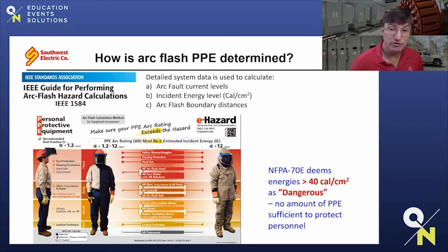This picture here gives you a visual on what kind of energies we're talking about. So the far left shows the very lowest energy levels regarding arc flash, 1.2 calories per square centimeter. Those are the units that they measure by. This equates to a second degree burn, so it's the amount of heat that would allow you to get a blister on your skin. That's what 1.2 calories per square centimeter represents.